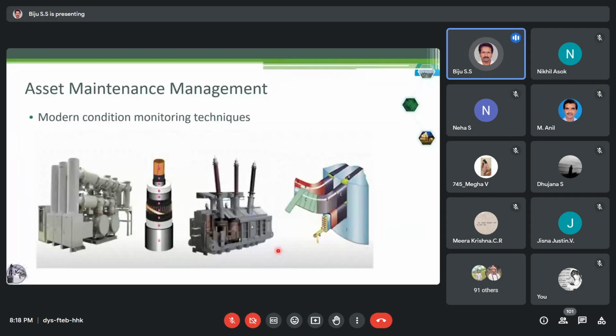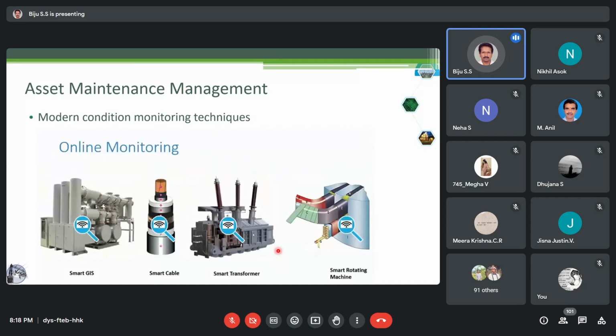You can have either offline mode or online mode for condition monitoring. Offline mode means you have portable analytic kits which you take to the equipment and do the analytics. You measure the things, bring it to your server, upload this data to the server, and do the offline models. That's always there for normal routine maintenance. But again, you can go for online monitoring, wherein all these devices become smart. Your GIS, your AIS, your smart cables, your transformers, your generating machines, everything can become smart. It will be Wi-Fi connected basically, where you have sensors integrated with the Wi-Fi connectivity.